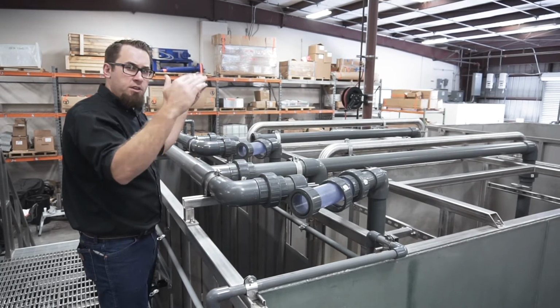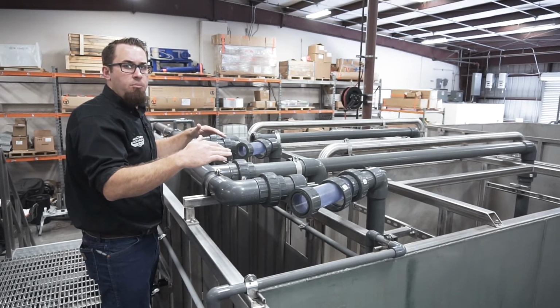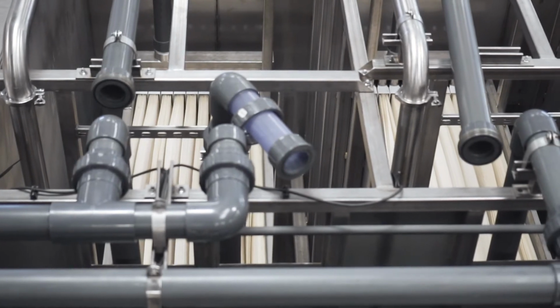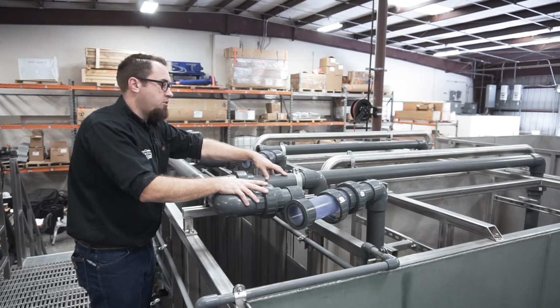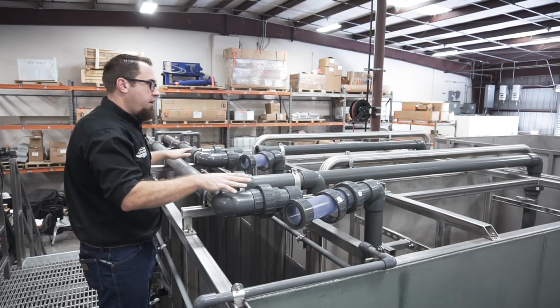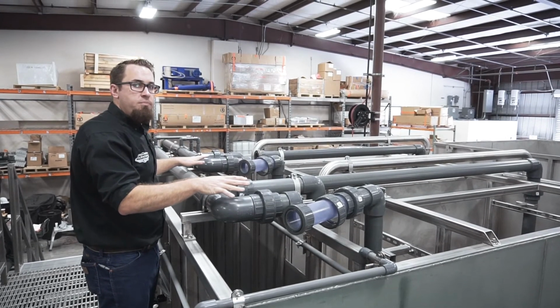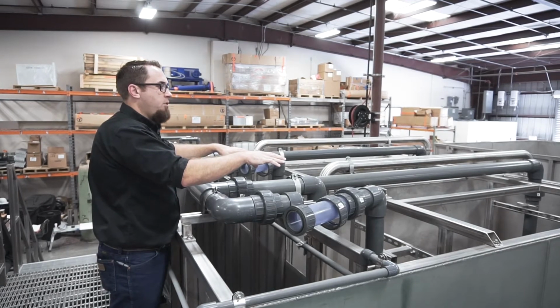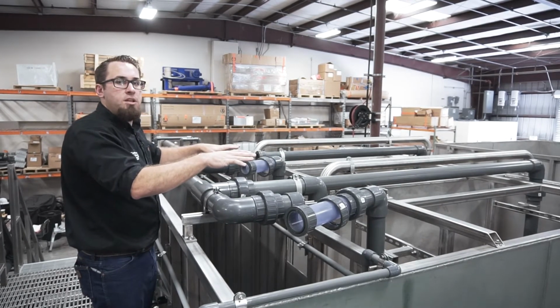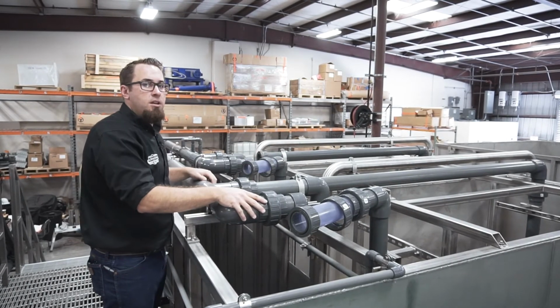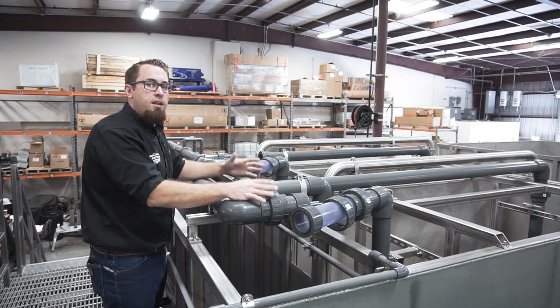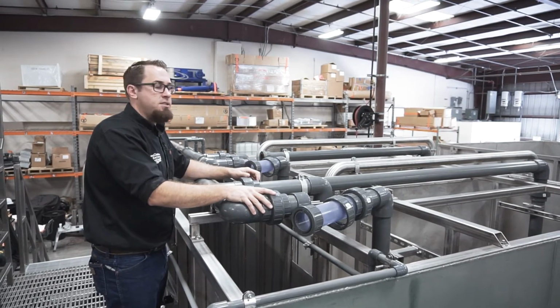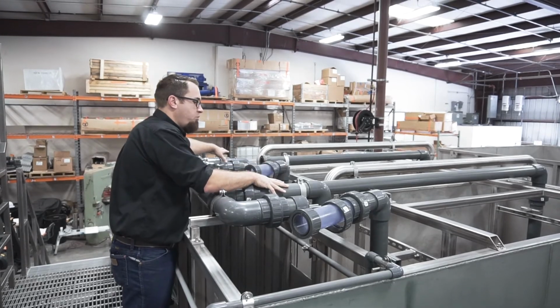As a result, we have a lower propensity to actually sludge the membranes. This particular side of the manifold is capped off, and you'll notice we have an open pipe that goes into the membrane chamber. This allows us to run the membrane permeate system without being hooked up to the membranes, so that we can test 100% of the program before we ever turn the membranes online. Once it's been thoroughly vetted, gone through its QC and QA process, and been signed off, we then remove these spools and tie in the actual membranes.